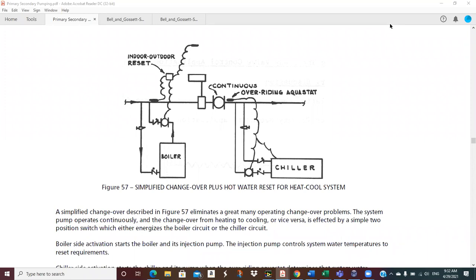But the interesting concept here you have to realize is that this would be for a two-pipe system. So a two-pipe system means I've got one coil in my space. I can put hot water through it and get heat, or I can put chill water through it and get air conditioning, but I can't do them both at the same time. And so this shows a central piping system that has a boiler and a chiller connected to it. And of course, to save money, there are systems, schools, for example, that it can be chilly in the morning and they need to provide heat to the campus. But then later on, past 10, 11 o'clock, it starts heating up. And then with all of the people in the rooms, the cooling load becomes significant.